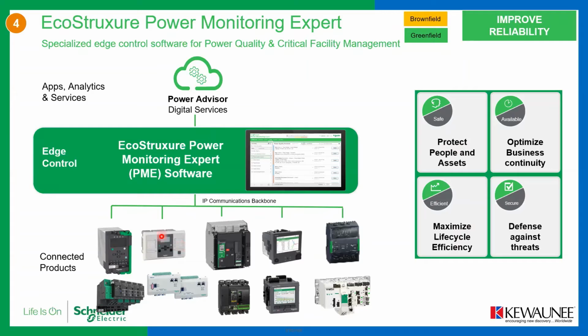That means these breakers or electrical distribution equipment are digitally connected to the software platform. We can get the complete settings of these particular breakers. For example, these breakers run standalone in different electrical distribution or various distribution panels. We can get this data through an IP backbone and bring it into a centralized platform. This can help you know that this breaker has a problem, these are the settings, a power event happened, these are the sequence of breaker tripping and failure. So this can be really tracked.